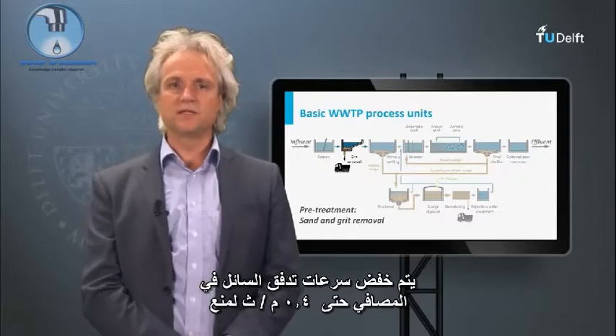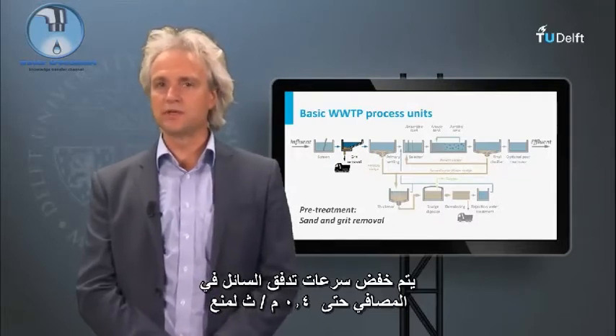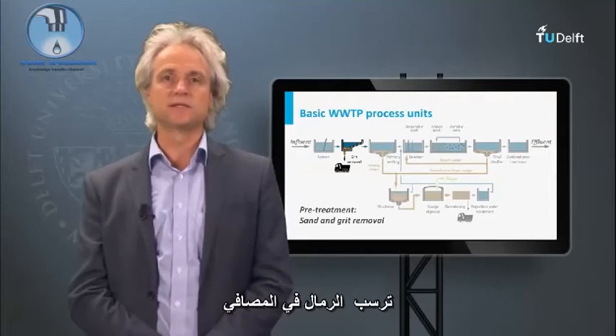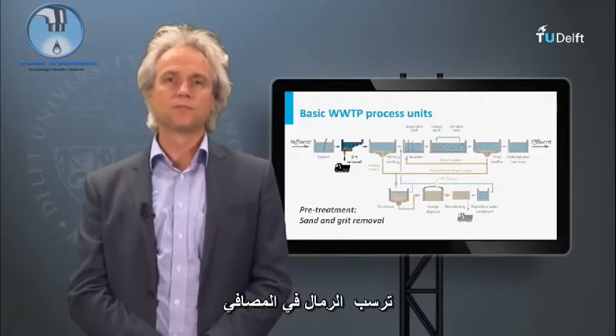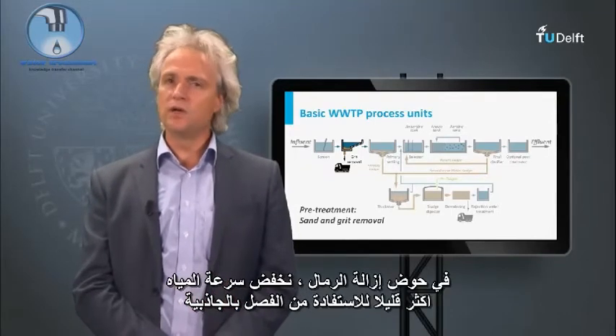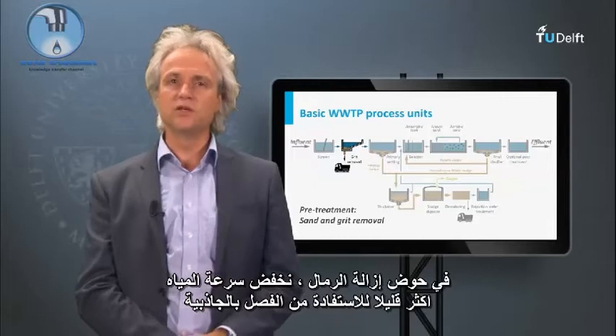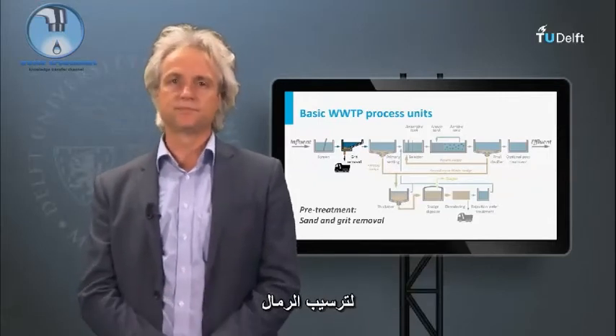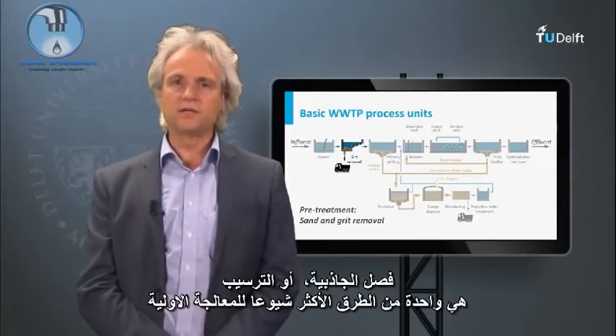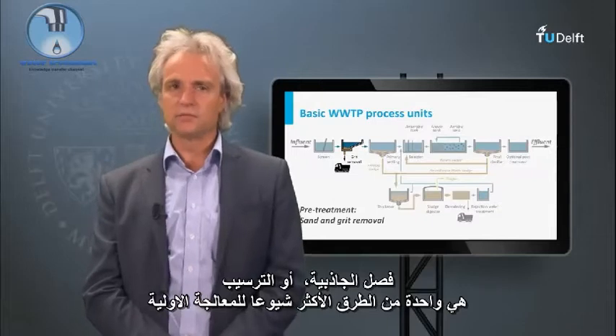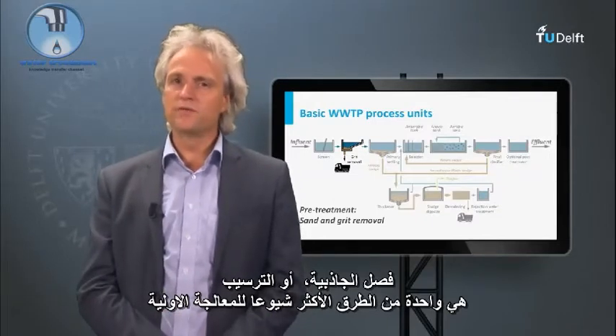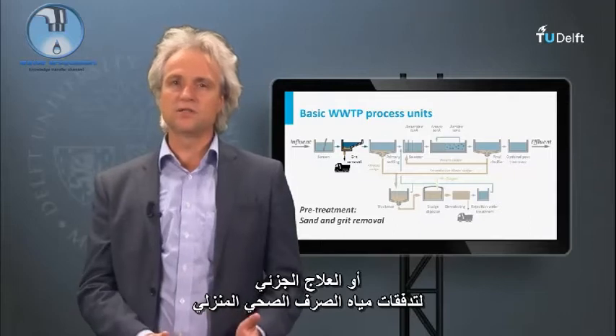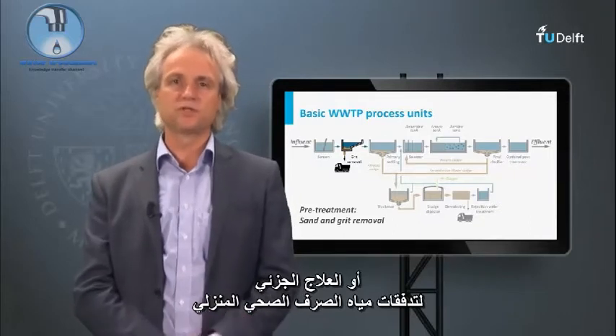Lowering of the liquid velocities in screens is restricted to 0.4 meters per second to prevent sand from settling in the screens. In the grit removal device, we lower the liquid velocity a bit further to make use of gravity separation to settle the sand. Gravity separation, or settling, or sedimentation, is one of the most common approaches to pre-treat or partially treat domestic and municipal sewage flows.